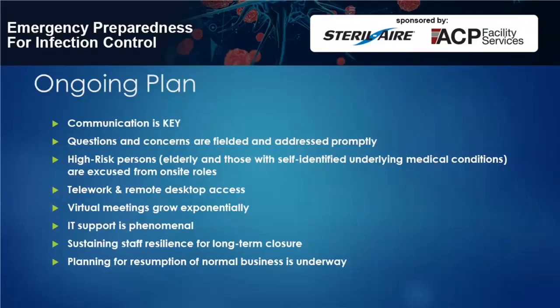Okay, great. Another question for Josh. Are there portable or temporary UV air systems that can be deployed in spaces without requiring installation? There are. But with that said, the amount of energy you need to really disinfect a certain amount of space depends on where the application needs to be. The application downstream of a cooling coil offers two different things that are beneficial. Not only are you disinfecting the air, but you are disinfecting what ASHRAE regards as a disseminator of pathogens in a building. Your cooling coil grows bacteria and mold, yeast, and other things.